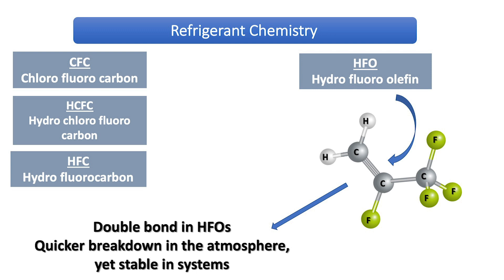The one unique property that the olefin gives the HFOs — that makes them different from the HFCs — is a very short atmospheric lifetime. That olefin is very amenable to reacting with hydroxyl radicals if it were to leak out into the atmosphere where there are hydroxyl radicals present. Those hydroxyl radicals will break down the HFOs, so it has a very short atmospheric lifetime and very little chance to impact the environment.